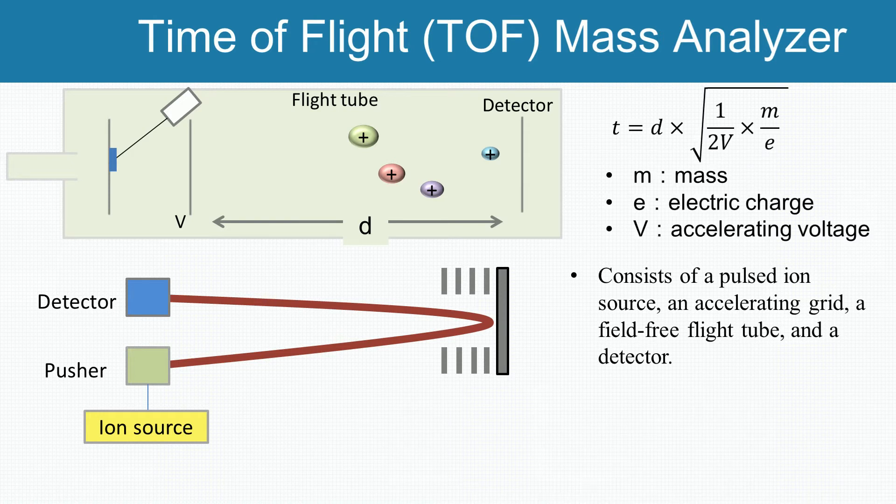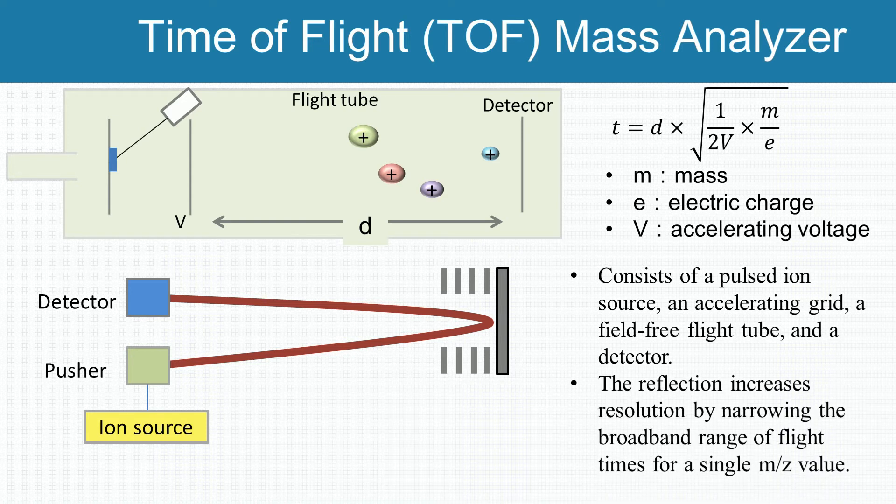At high masses, not all the ions of the same mass-to-charge values reach their ideal velocities. To fix this problem, often a reflector which consists of a series of ring electrodes with high voltage is added to the end of the flight tube. Because of the high voltage, an ion is reflected in the opposite direction when it enters the reflector. For the ions of same mass-to-charge value, faster ions travel further than the slower ones into the reflector. In this way, both the slow and fast ions of the same mass-to-charge value reach the detector at the same time. The reflector increases resolution by narrowing the broadband range of flight times for a single mass-to-charge value.